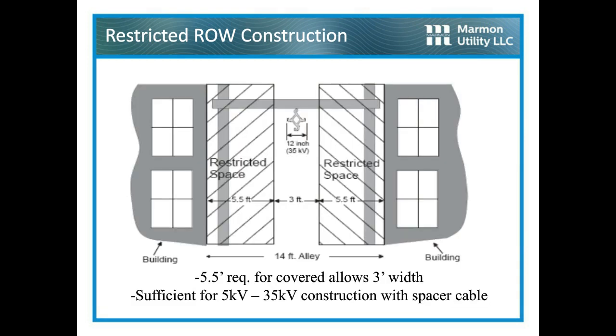So this is a typical project you would have in a 5 to 15 or a 5 to 25 or whatever voltage upgrade in an alley. So if I needed 7.5 feet for bare wire, it wouldn't fit. So I'd only be able to go underground, which is always a good option, but sometimes a little bit expensive, or bare wire, which NESC says I need to be 14 feet above the rooftop.